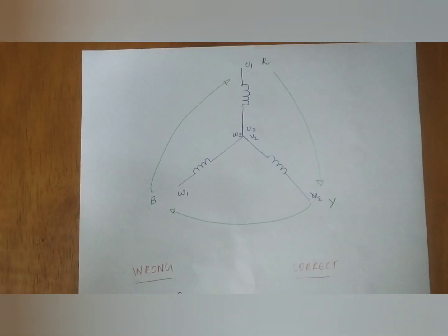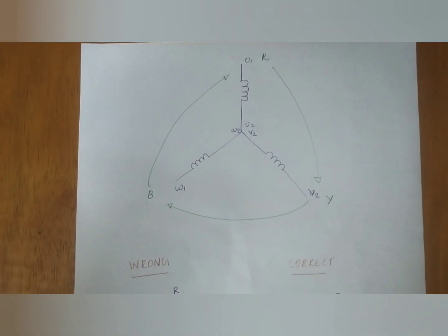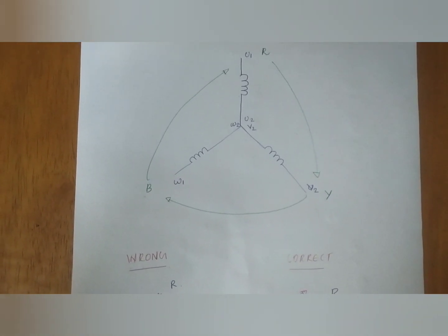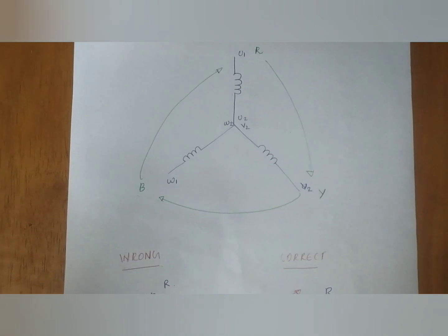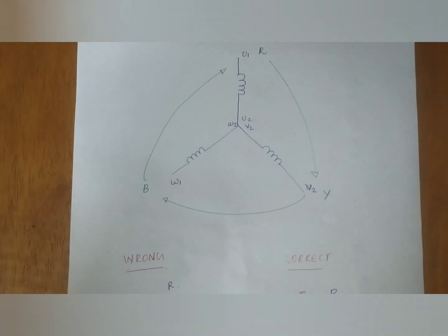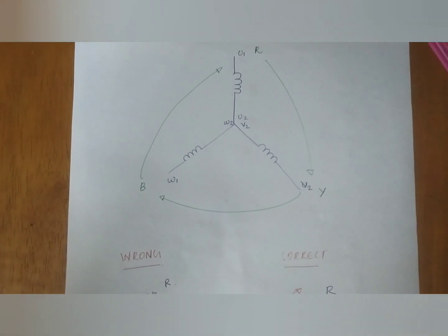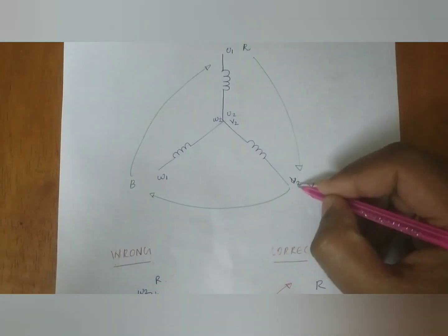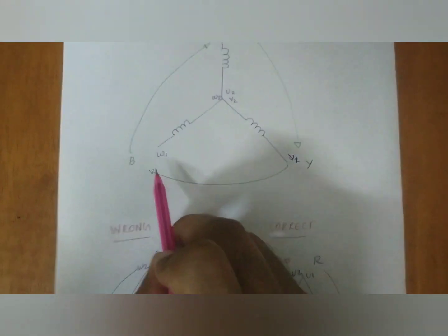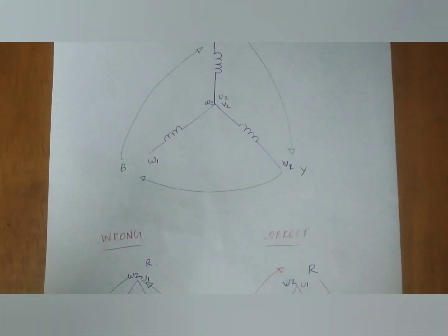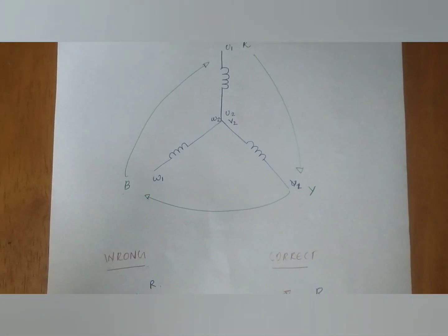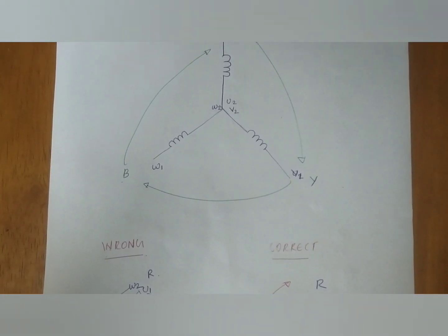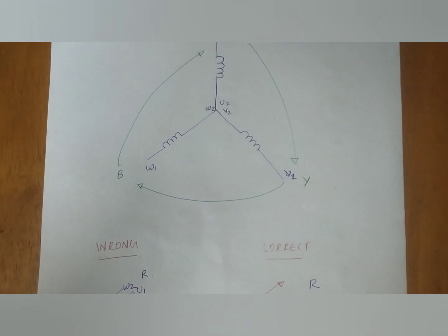Now let's see a problem that most electrical engineers would have faced while working with the star delta starter. That's nothing but tripping of a contactor. Let's see it in detail. During the start, let's assume that U1 is fed with the red circuit, V1 is fed with the Y circuit, and W1 is fed with the B circuit. In this condition, the motor will be working in clockwise direction, and once it is turned on to delta, the motor might suddenly trip.